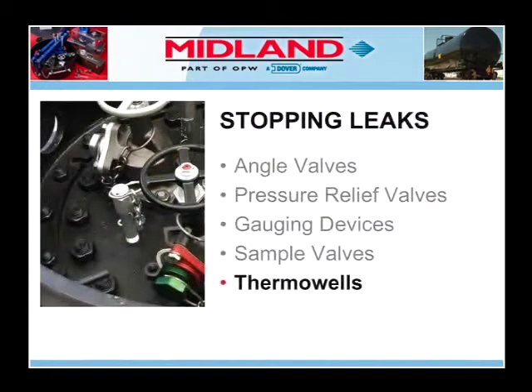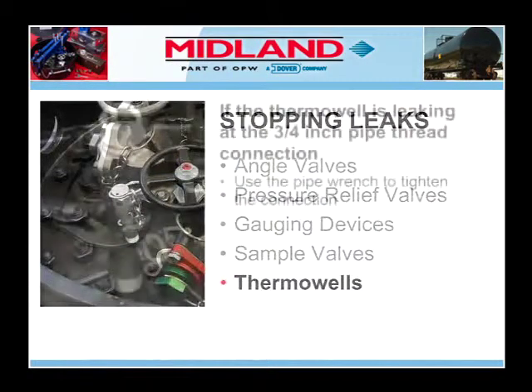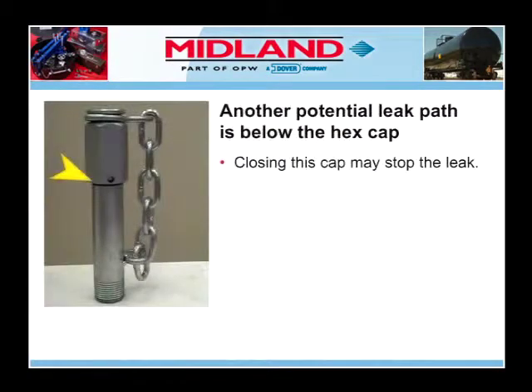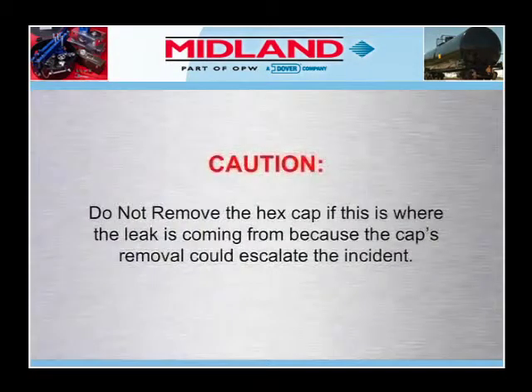Next, we will examine stopping leaks from thermowells. If the thermowell is leaking at the three-quarter inch pipe thread connection on the cover plate, use the pipe wrench to tighten the connection. Another potential leak path is below the hex cap at the top of the fitting; further closing of this cap may stop the leak. Caution: do not remove the hex cap if this is where the leak is coming from, because the cap's removal could escalate the incident.